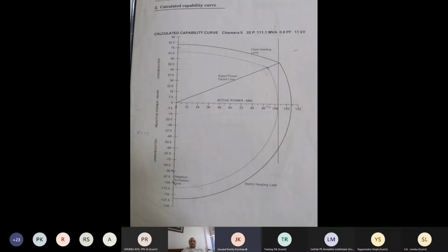Sir, in over excitation, flux is more than the required. That's why the field winding, I think. Flux is not more than required. The field current which is supplied generates the required reactive power within the capability curve. There is a limit, but it is still within the capability curve, till you hit the ceiling of the characteristic where the over excitation limiter will prevent you from increasing the field current further.